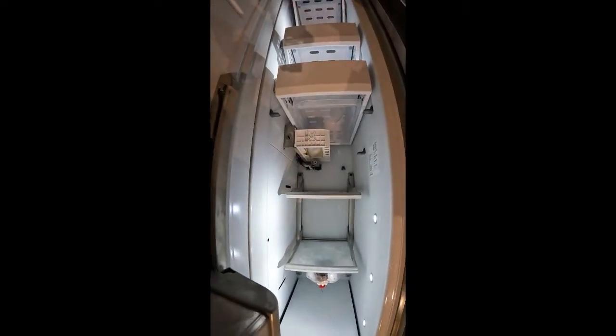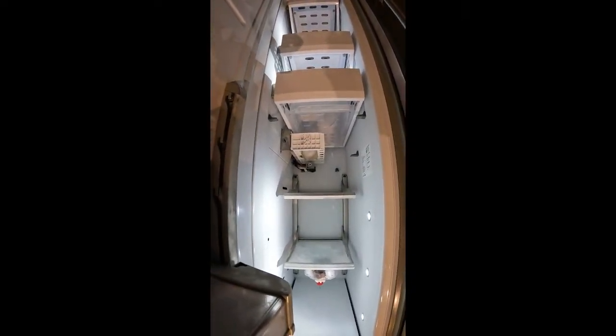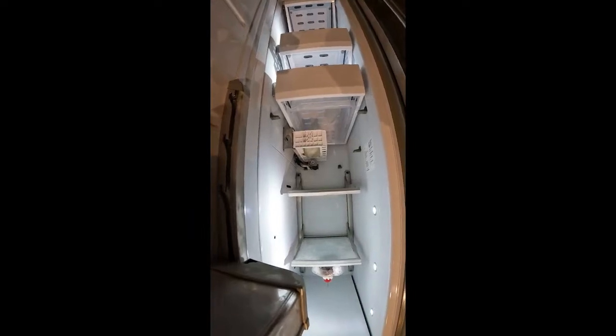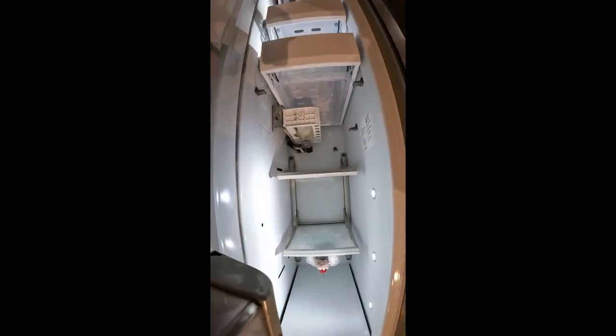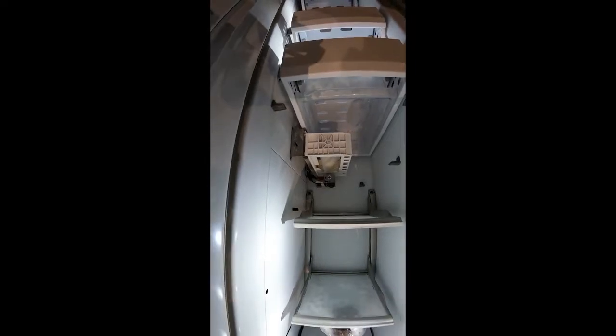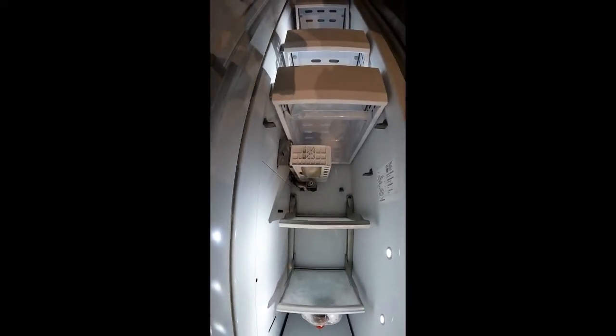So you can see it harvests twice, and then the ice maker actually sits sideways like that. If you want to pan in a little bit closer, you can see how the ice maker is sitting sideways. This is to allow the water to trickle through the ice maker and drop into the ice bucket so it doesn't fill with one big giant sheet of ice and then have trouble kicking that ice out during the next harvest. So at this point, the user interface will say start cleaning, push enter.